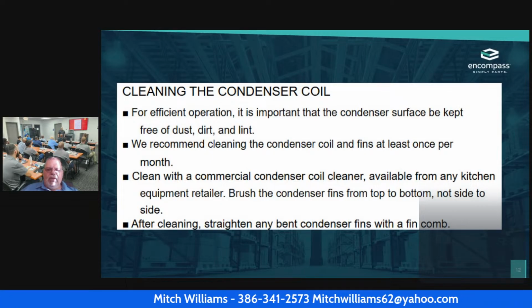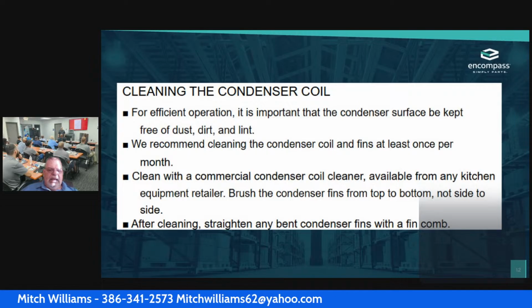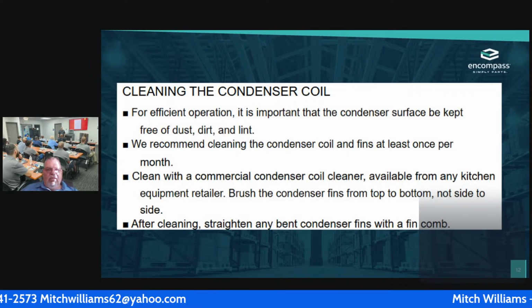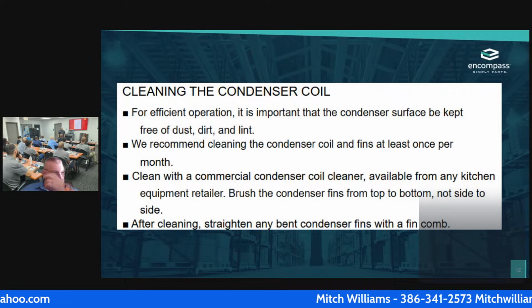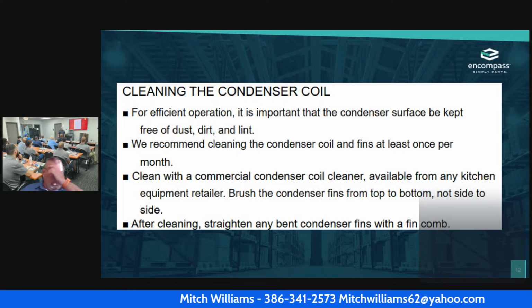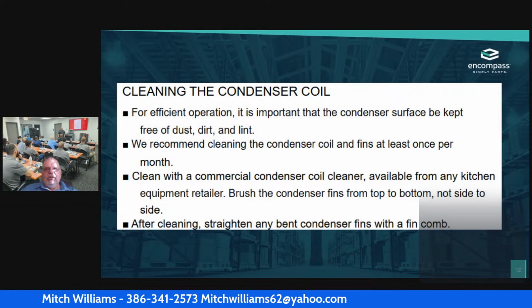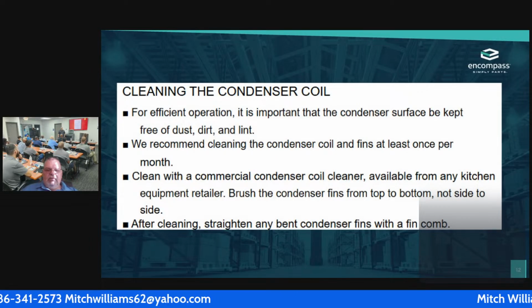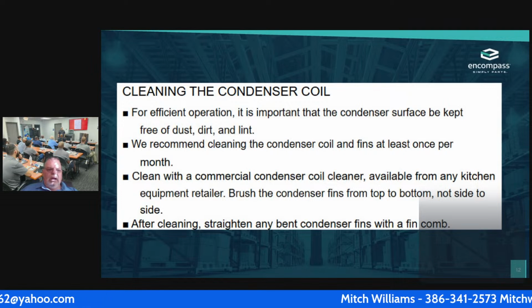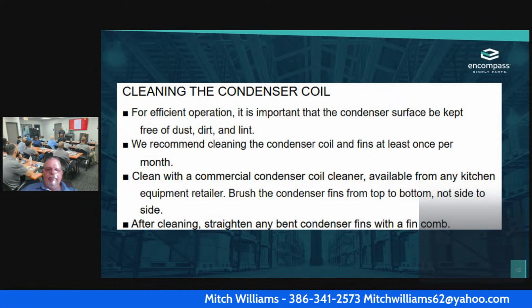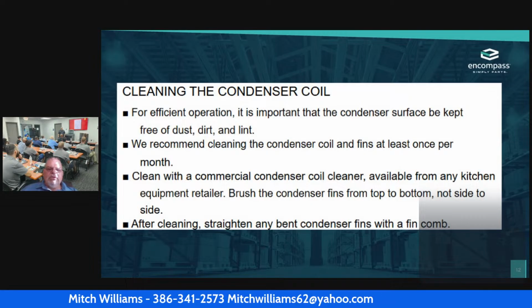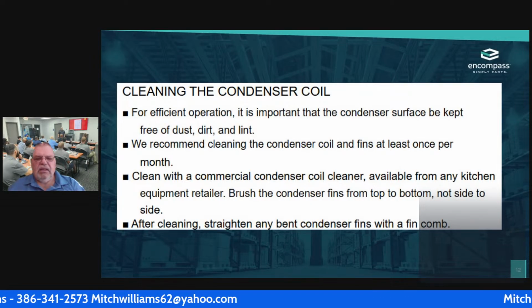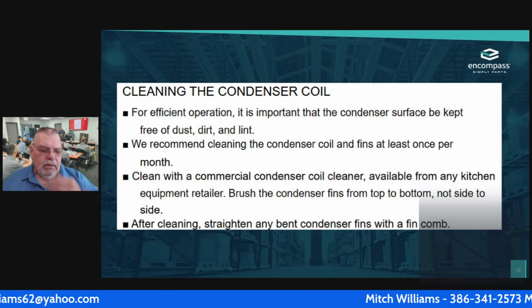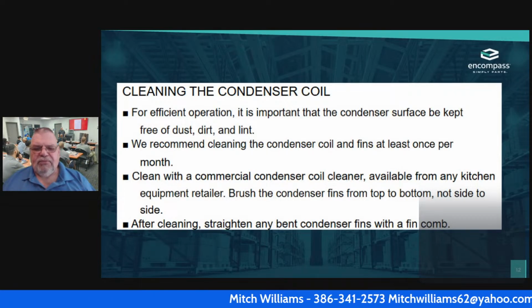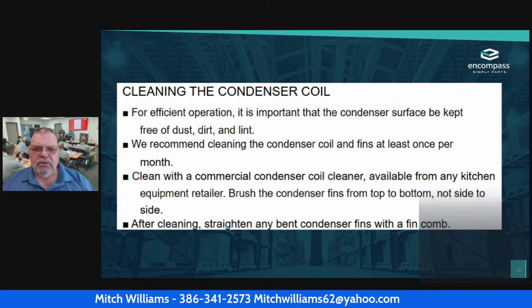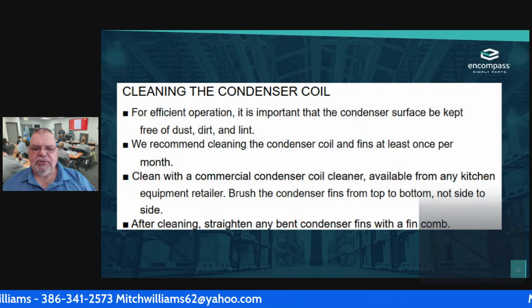After I do all of that, I'm going to make sure that I get all the way through. I'm going to shine a light in the back of that, looking at the condensing coil, making sure that I can see light all the way through it, especially if it's near something that produces moisture or high temps, like the fryer. So I'm gonna do all that. Once I get done, after I do that, I've got to clean it. If I've got anything that's bent on these coils, I'm going to have to use a fin comb to keep it from damage.